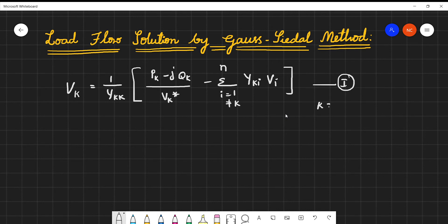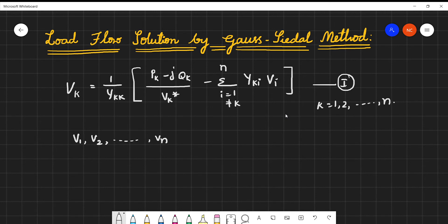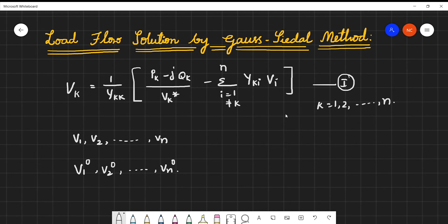We have an n-bus system. In the Gauss-Seidel method we need to consider initial guesses for all the node voltages: V1, V2, and so on up to Vn. Initially we are not discriminating by bus type — whether slack, generator, or load. Generally, we can assume all node voltages with initial guesses denoted as V1⁰, V2⁰, and so on up to Vn⁰, and we will start with these initial guess values.